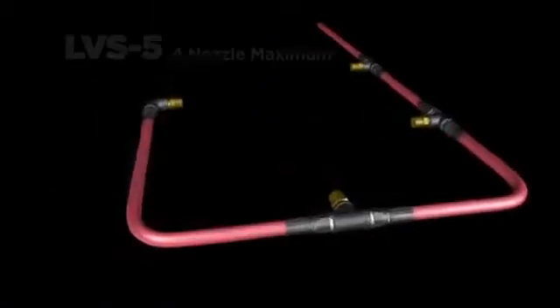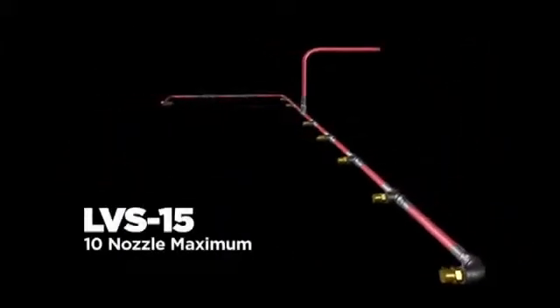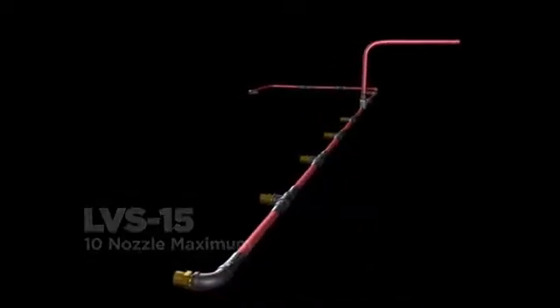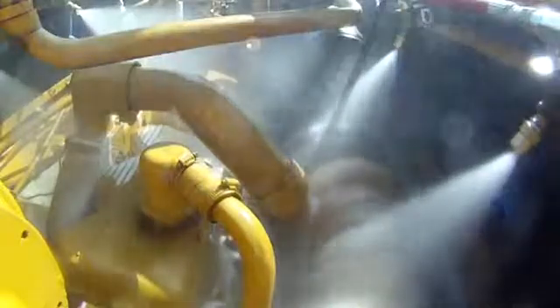The LVS-5 allows for a maximum of four nozzle protection. For larger equipment, the LVS-15 and LVS-30 can be configured to a maximum protection scheme of 10 and 20 nozzles respectively. The Ansul Liquid Vehicle System provides constant nozzle pressure and a full discharge pattern throughout the duration of the discharge — a full 30 seconds with the LVS-5, while the LVS-15 and LVS-30 will discharge for 60 seconds.